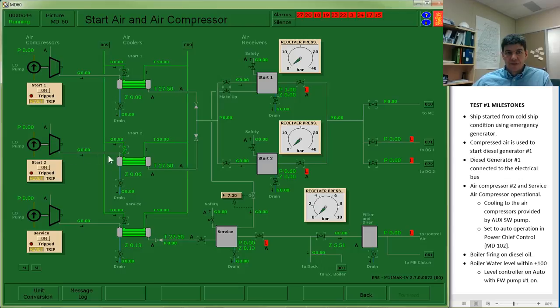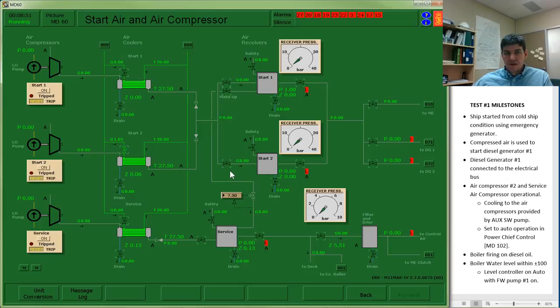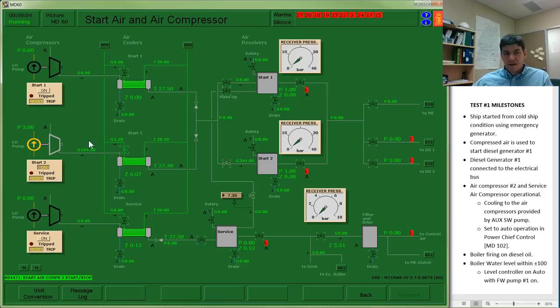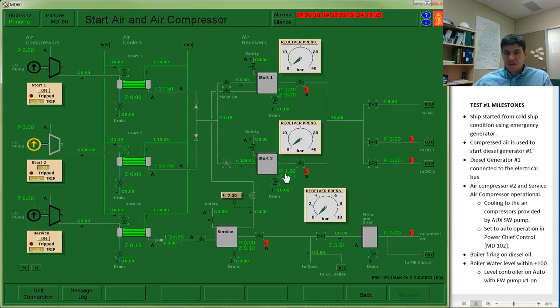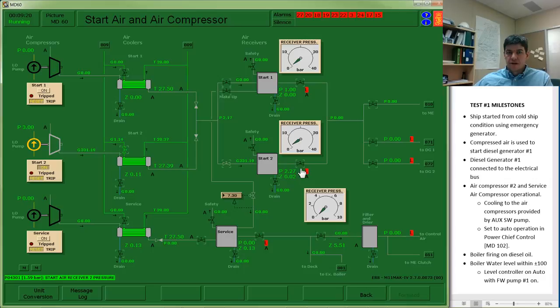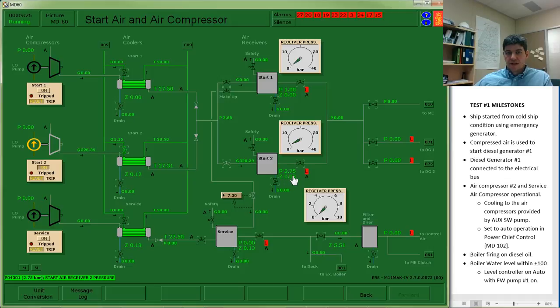If I go to my air compressor page, I'll see that I am getting some cooling water flow through my after cooler. So at this point, it's going to be safe for me to operate this air compressor without it risking overheating. My pathway comes through. I'm going to fill up one of my tanks. So if I choose to fill up my start air number 2 tank, I'm able to turn on my start air compressor number 2. It is now supplying air and my start air tank number 2 or receiver is starting to increase in pressure.